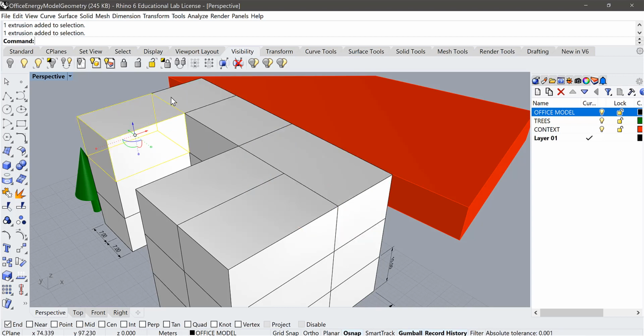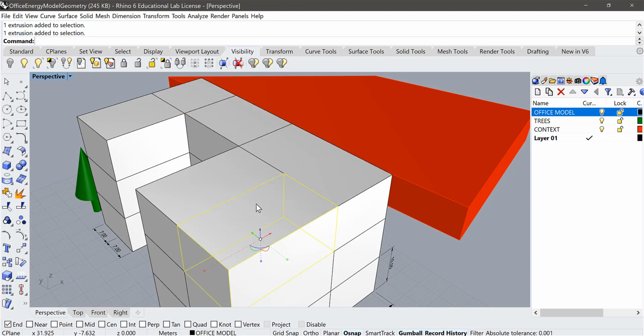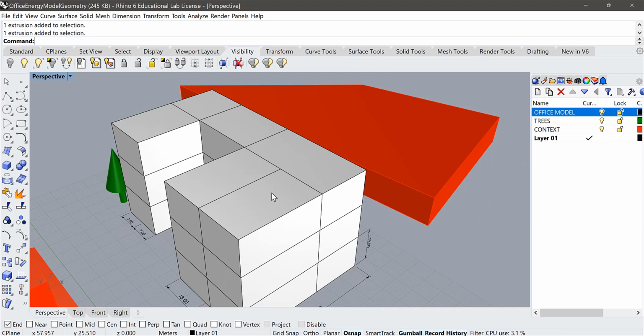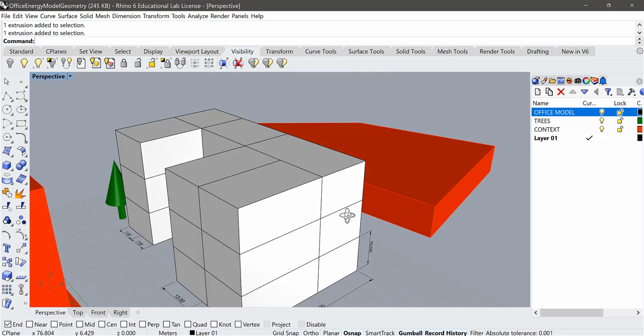So that's why we split the building into different zones, so you can have the maximum control, with a different thermostat in each energy zone to control each zone individually. And this also helps maximize energy savings in buildings. So in reality, a big floor like this usually has about 6 zones or different types of zones to control temperature set points in the summer and in the winter individually. So I split each floor into 6 zones. So now I have 18 zones in the whole entire building.